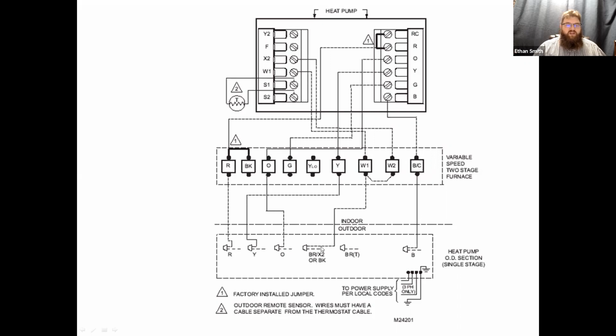One thing you'll notice is there's usually a black wire in the outdoor unit that is wired into the heating system. That wire is our defrost signal. When the outdoor unit fires, we want to bring the electric heat on so that when we go into defrost, that does not cause the unit to cool off the house. We want to bring the supplemental heat on so that the cooling effect generated off of a defrost cycle won't cool the house down. We're going to use that supplemental heat to heat that air back up before it goes into the house. If you don't do this, your homeowners will get a nasty surprise. Every time the unit goes into defrost, they'll get a blast of cold air out of the ductwork and it'll be pretty miserable. And you guys will get a phone call.